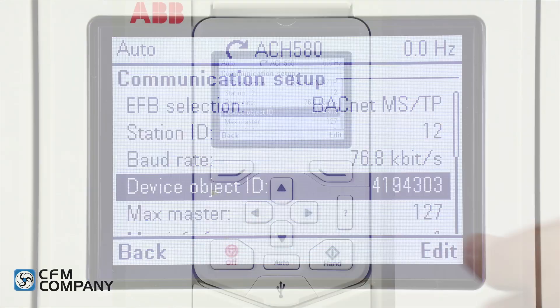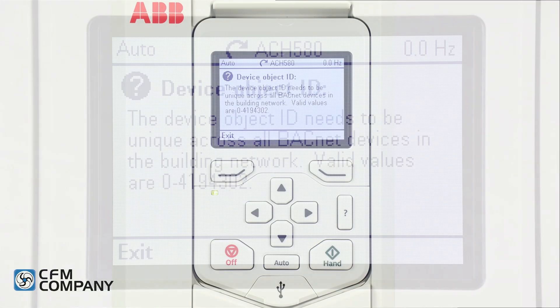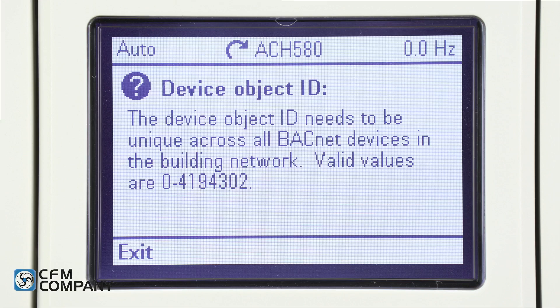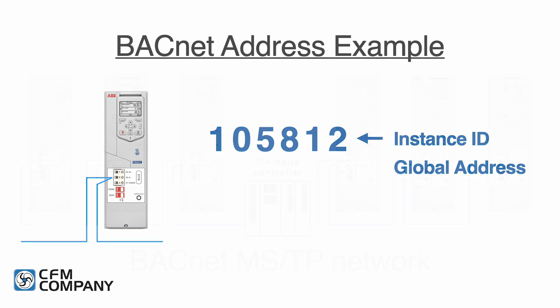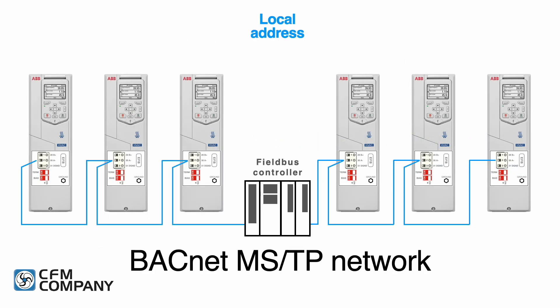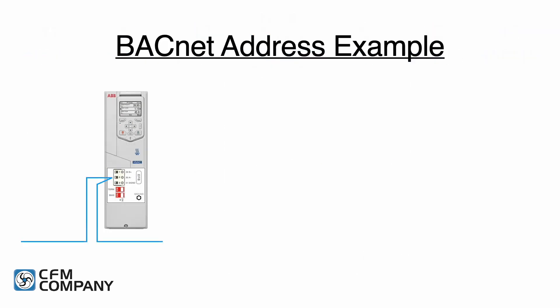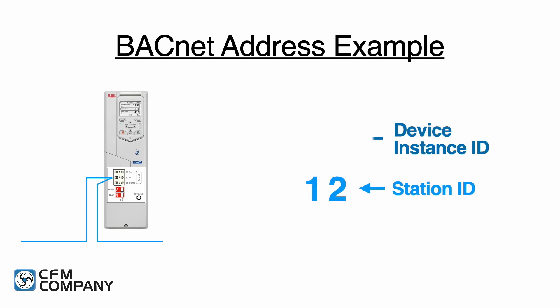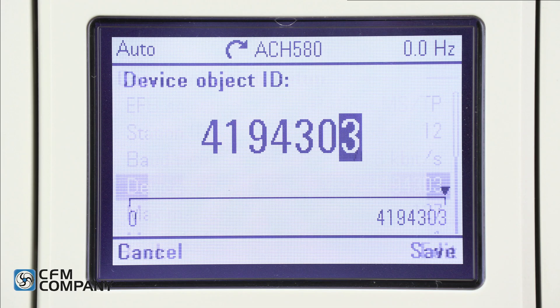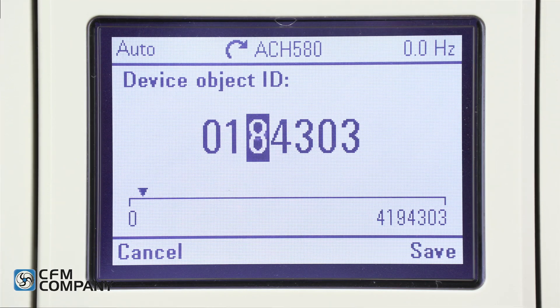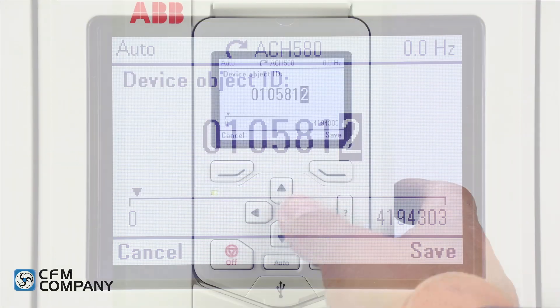Next is the device object ID. Press the question mark button to get more information. The device object ID needs to be unique across all BACnet devices in the building network. For this video, the instance ID is 105812. The instance ID can also be referred to as the global address. For a BACnet MSTP network, there must be both a local address and a global address for each device on the network. In the ACH 580, these are referred to as the station ID and the device instance ID. Press exit to return to the communication setup menu, then press edit at the device object ID, change the value to 105812, and press save.